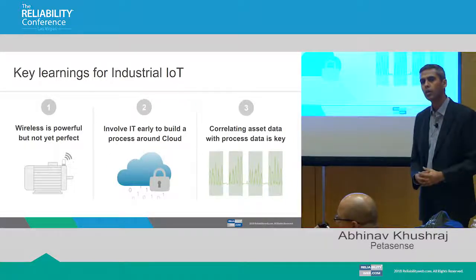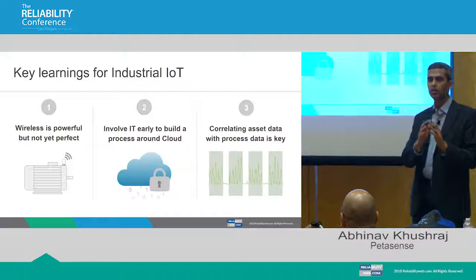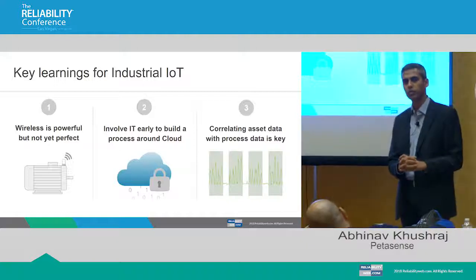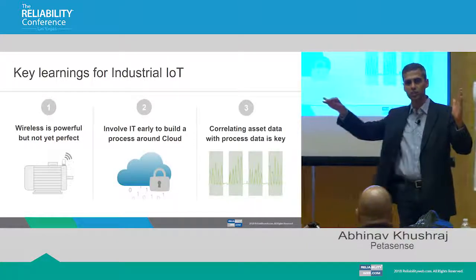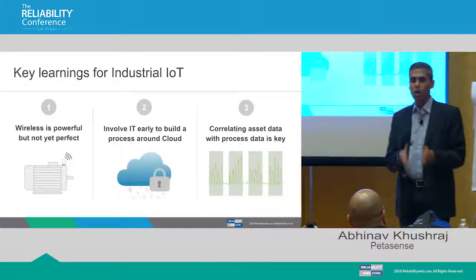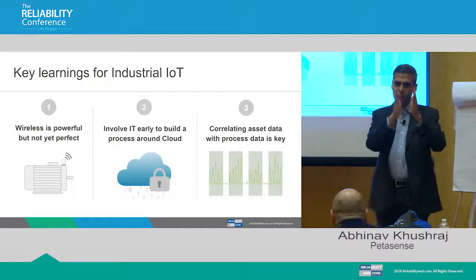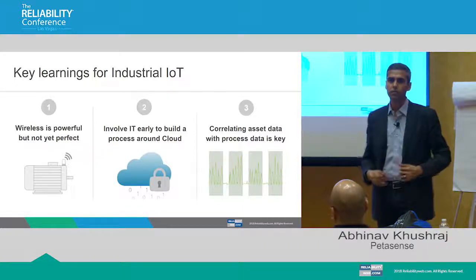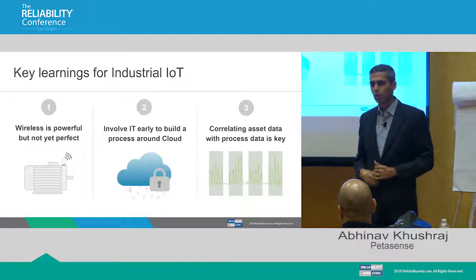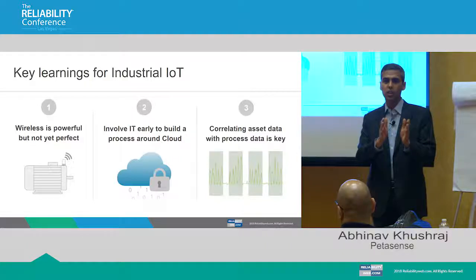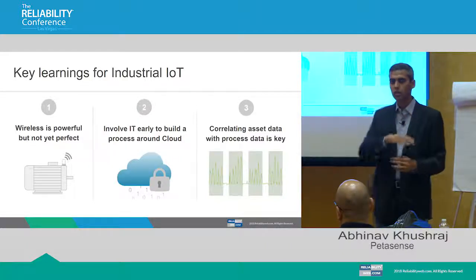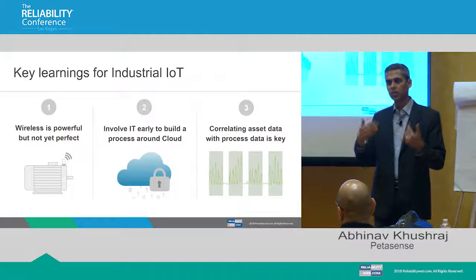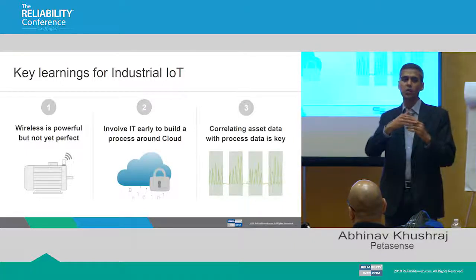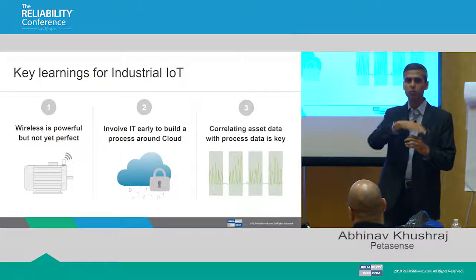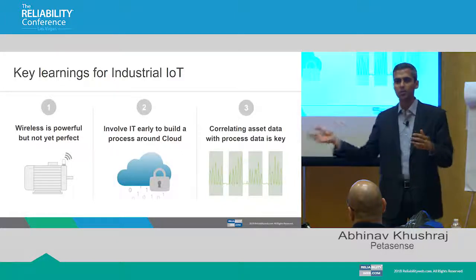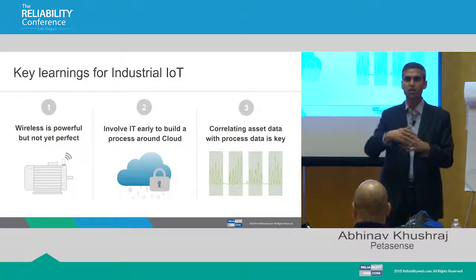Do you have band alarms you can put on these? Yes, we do band alarms, overall alarms, and envelope alarms. You can do overall alarms on RMS or peak for broadband features, or band alarms, like on your 1x to create a range. You can add as many bands as you want since it's just software. For envelopes, you can take one spectrum and set one standard deviation as a warning alarm, or two standard deviations as a critical alarm.